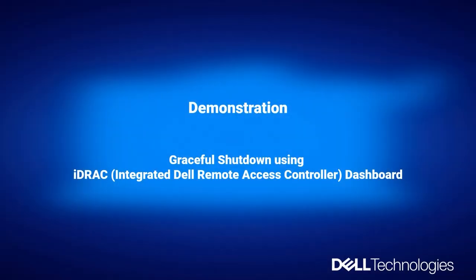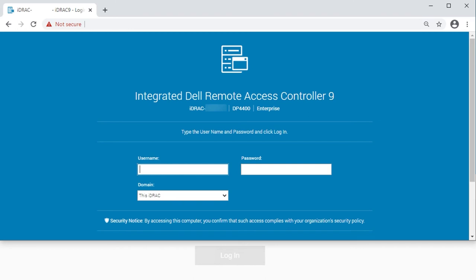After verifying that the appliance has shut down 100% in the ACM interface, you can perform the appliance shutdown using the IDRAC interface. Please perform the following actions to gracefully shut down the IDPA appliance. Open the IDRAC web interface and login.